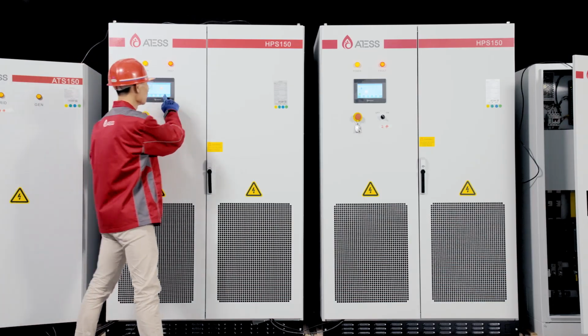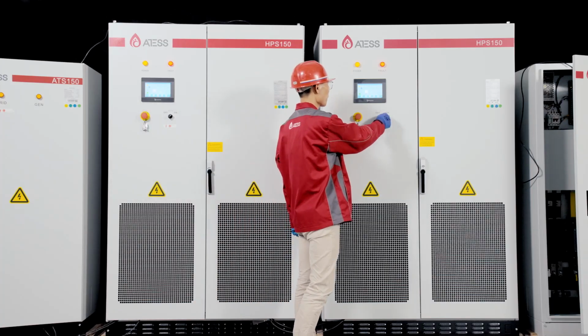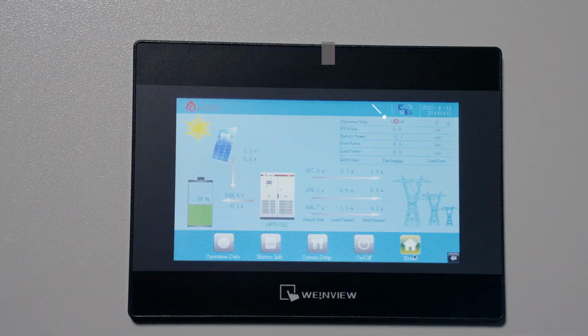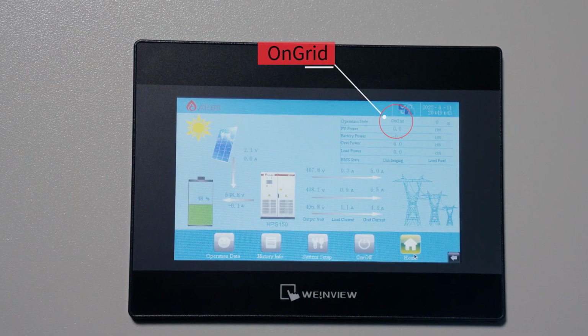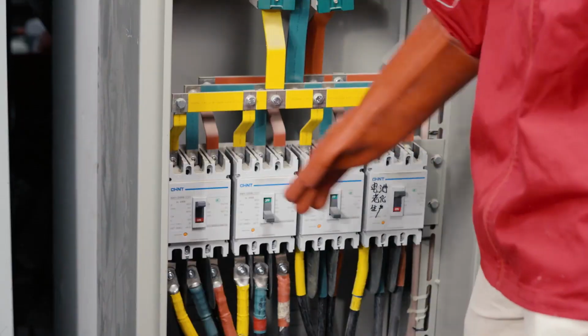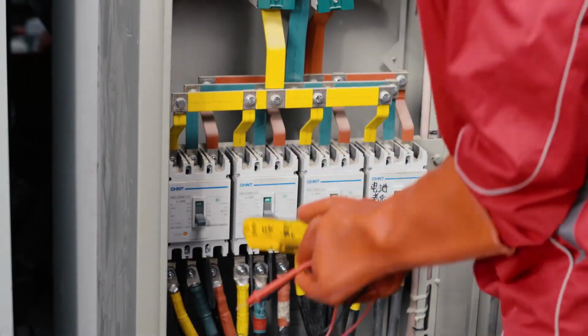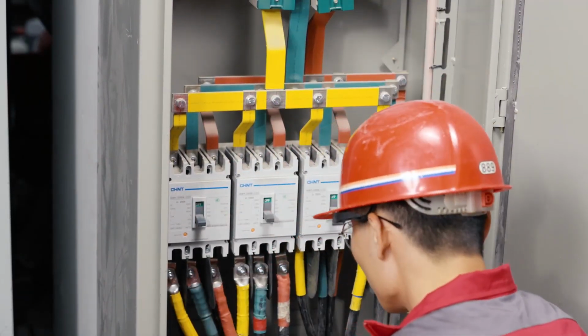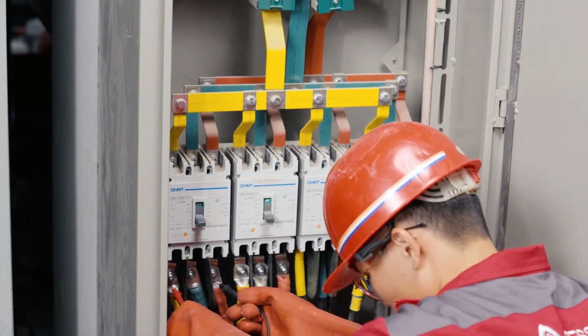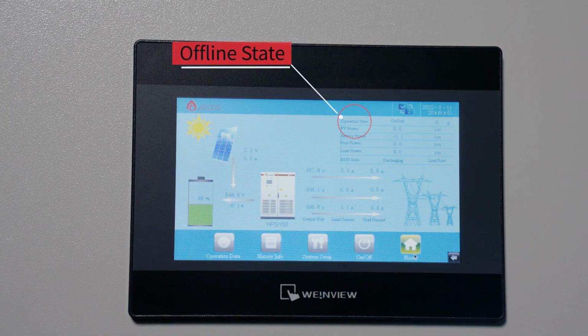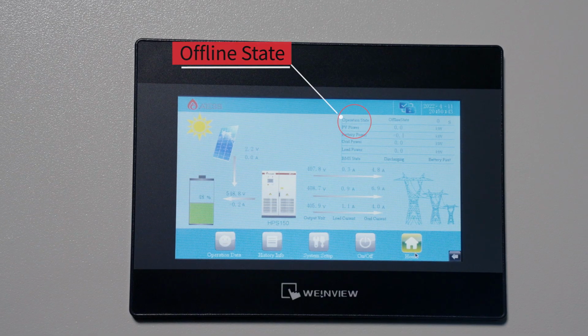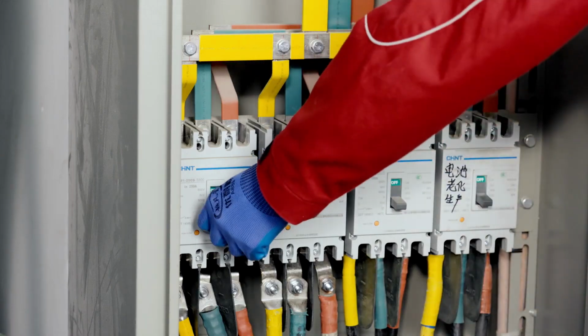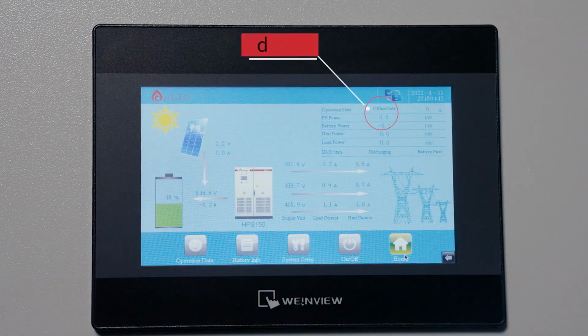Turn on the switch knobs of the two HPS. Click the power button on the screen. The two HPS work well in on-grid mode. Disconnect the external grid breaker. The two HPS switch from on-grid mode to off-grid mode. Close the external grid breaker. Then the two HPS switch from off-grid mode to on-grid mode.